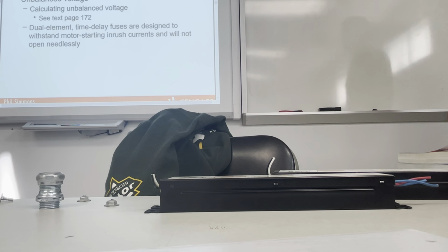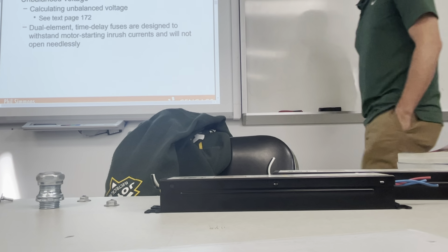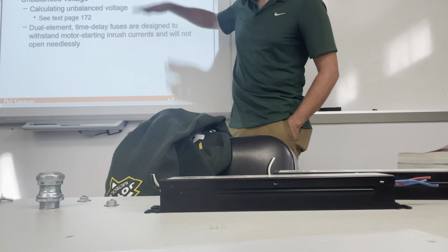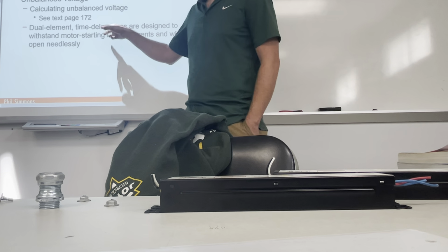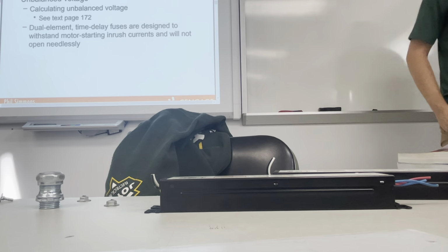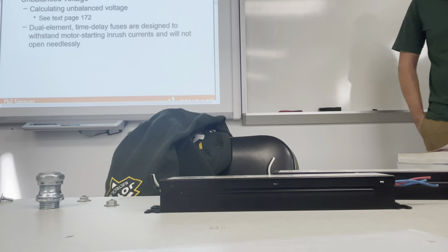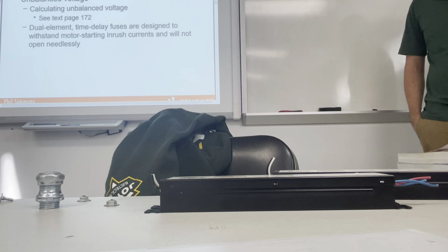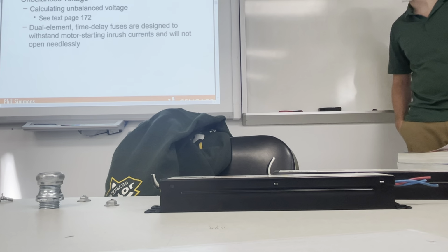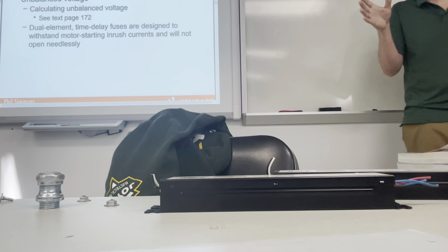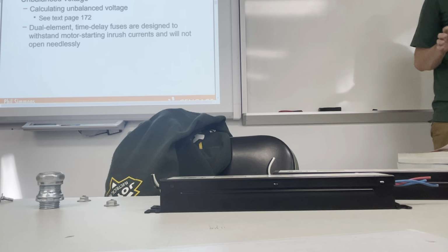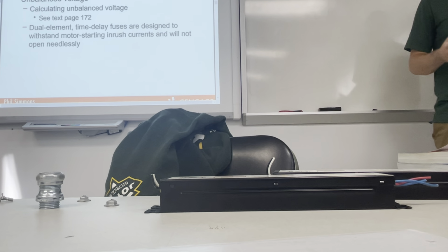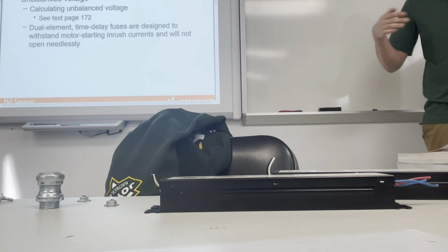See text page 172. Dual element time delay fuses are designed to withstand motor starting inrush currents and will not open needlessly. All right, so these are time delay fuses. I'm not talking about them in respect to unbalanced voltage, but that's another type of overload. You can have overloads that are just fuses, and they're set to pop with an X amount of delay. Let's say your fuse was rated to carry 20 amps, and you were pushing 20.5, just a touch over. It's going to let that go for say 300-400 seconds before it pops. Whereas if you're trying to run 30 amps, it would pop after 2 or 3 seconds. It's an inverse type of time.